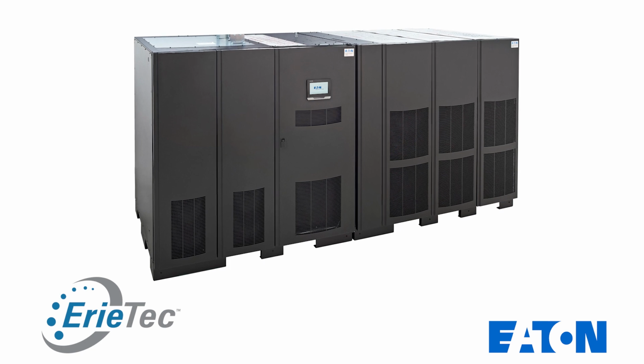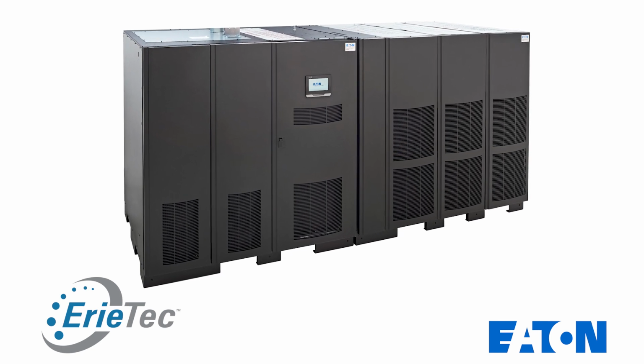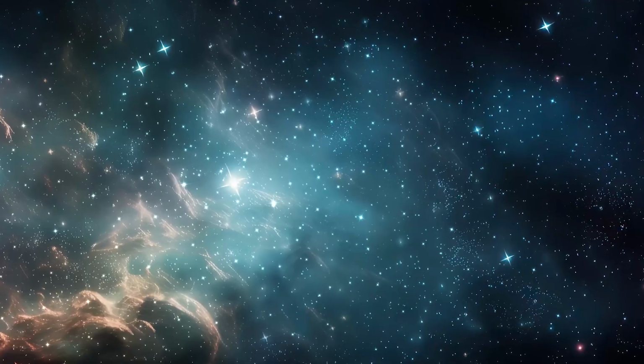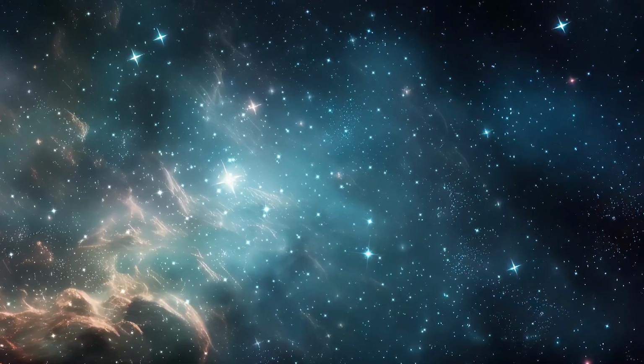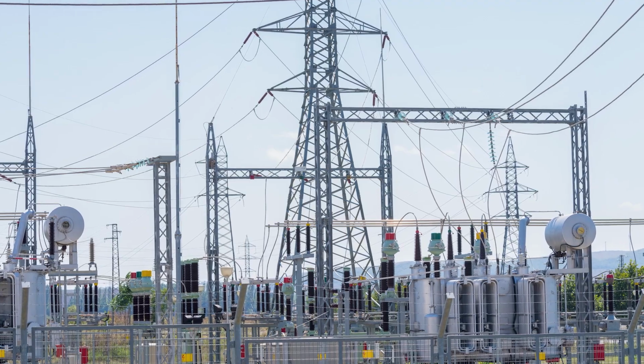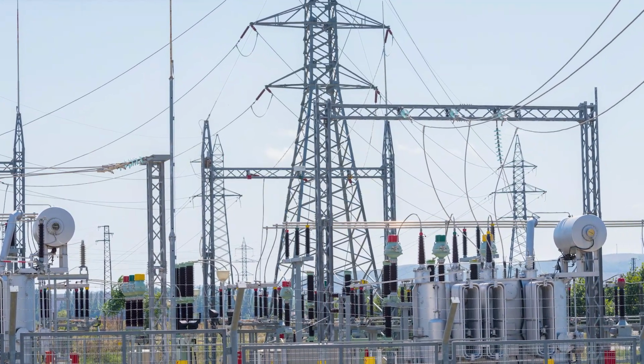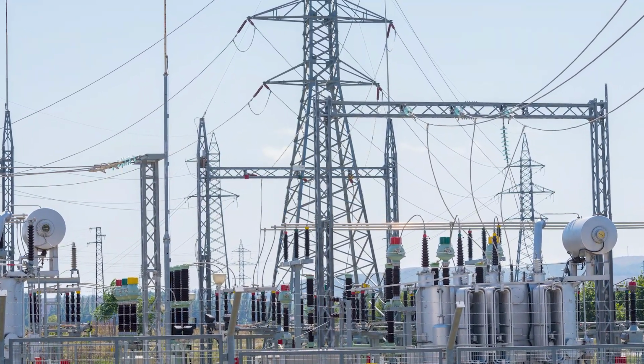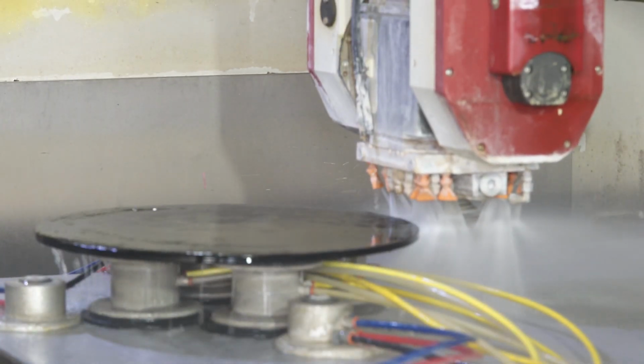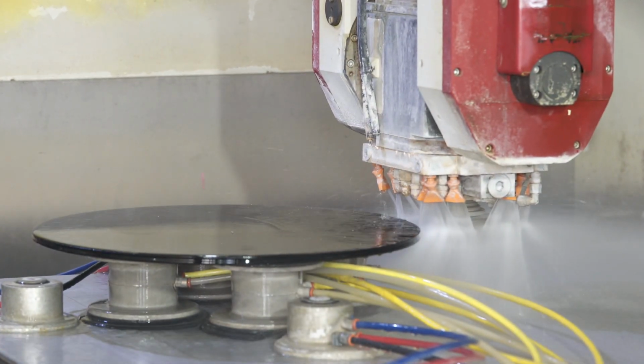The second one is a larger application. This one used a 275 kVA UPS, which is room-sized. It was an orbital polisher for a mirror for a space telescope. They were having problems with power quality with transients from local businesses in the area starting and stopping large motors, and they were also having trouble with reclosers interrupting power in the middle of the day. They asked us to provide a solution, and we came up with this UPS.